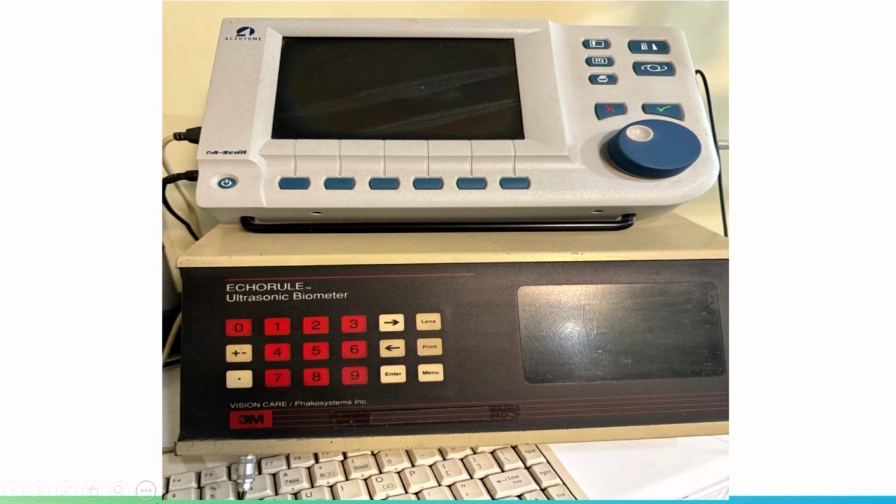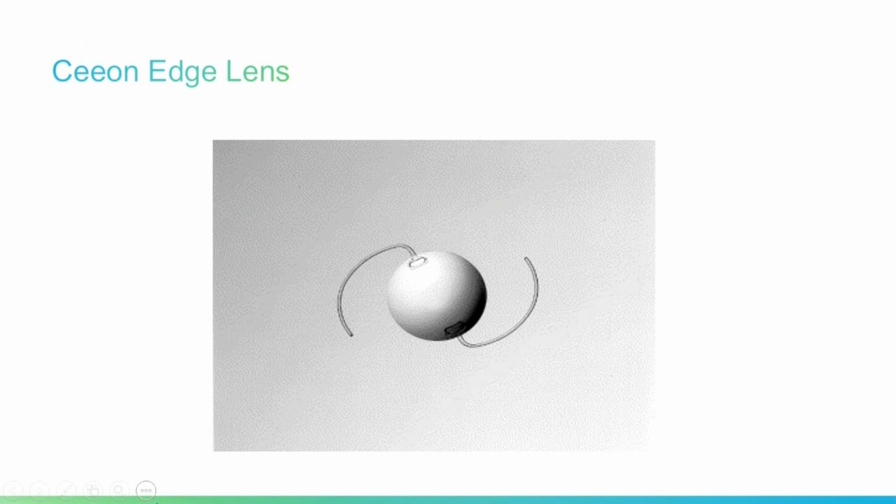That doesn't end there. When 3M was sold, the lens technology was bought by Pharmacia. Pharmacia continued selling that product as the 6.5 millimeter single piece lens for a short period on the CeeOn platform. Then they made this one. This is a monofocal. This is, in my opinion, the best lens ever manufactured in the world. It was silicone, but it had these funny loops. These loops were not circular in cross-section, they were rectangular. And the material was such that you can actually knot it, unknot it, and it will come back to shape. This was a lens that was way ahead of its times.